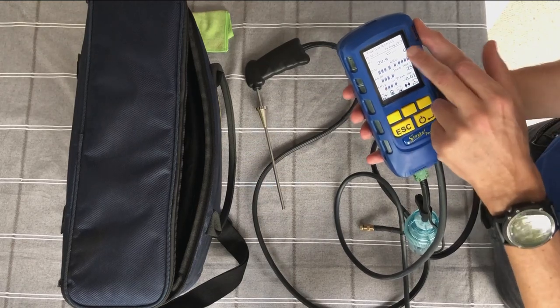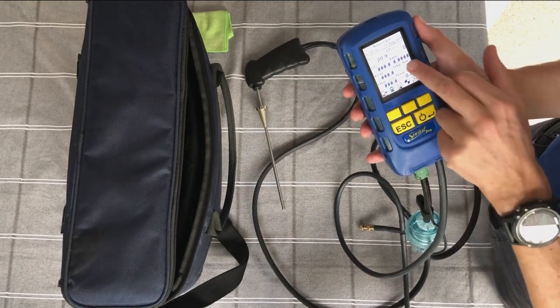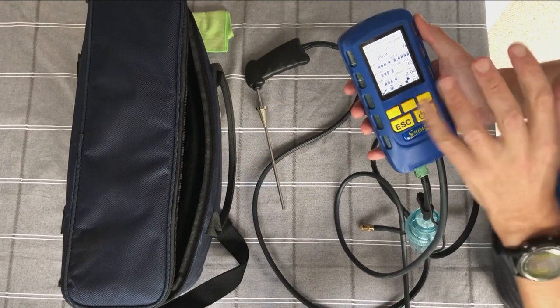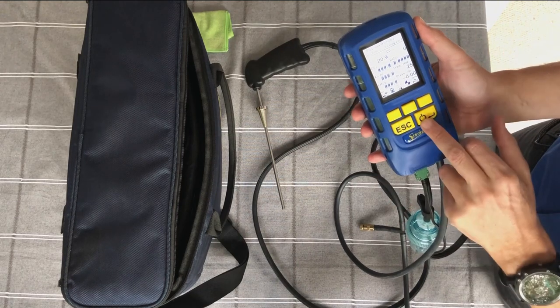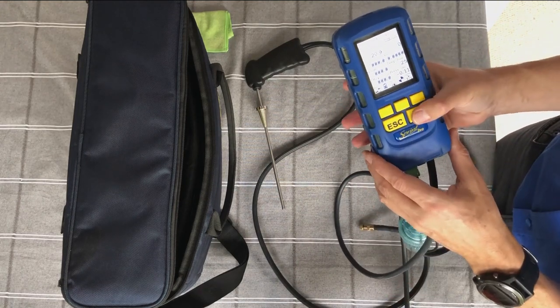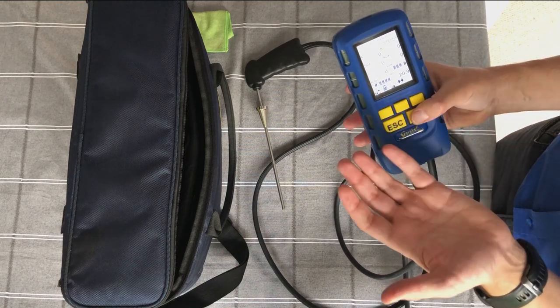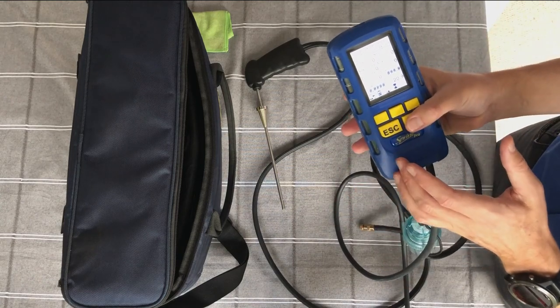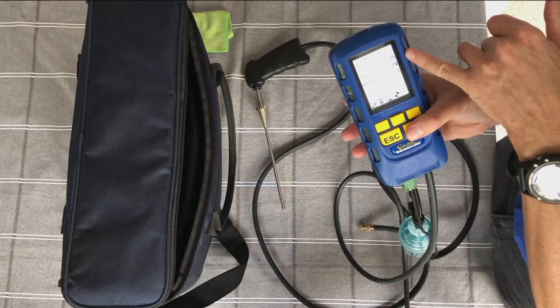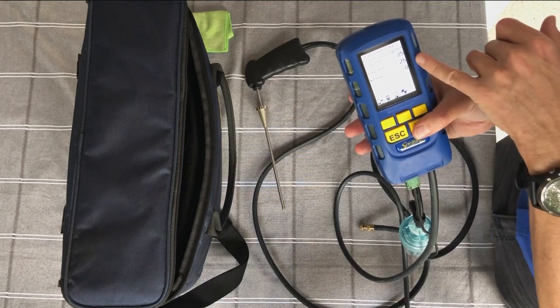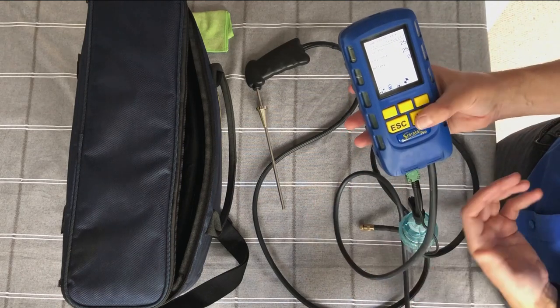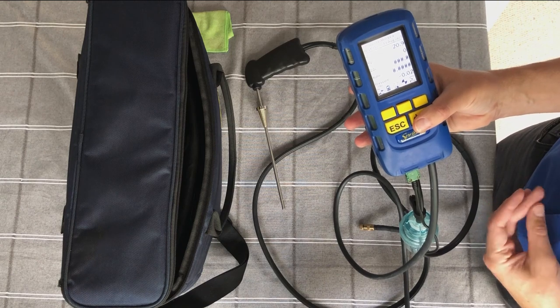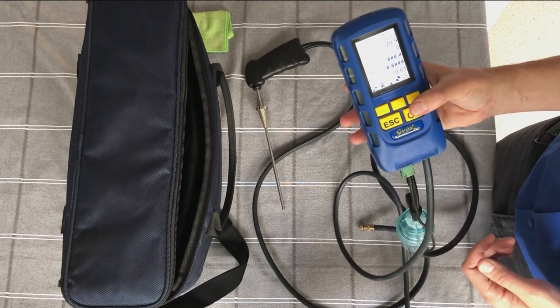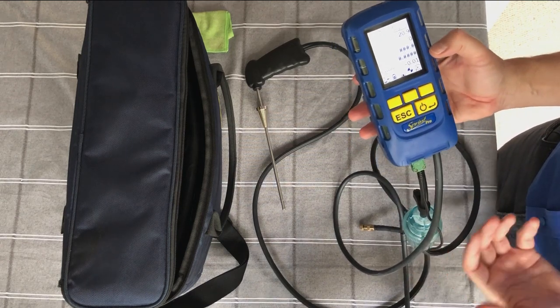So you've got O2, CO, CO2, the ratio, excess air, flue temperature, efficiency, and the pressure all on the one page. And then because I've got a Pro 6 here, I'm also getting my NOx readings and CO2 readings. Most people wouldn't have that. But then you get to this page, which is flue temperature, inlet, and the ambient. There you go, and then the differential, in case you're interested.